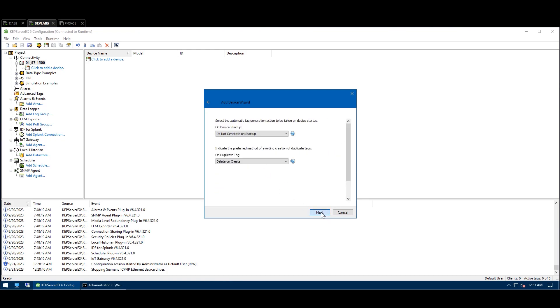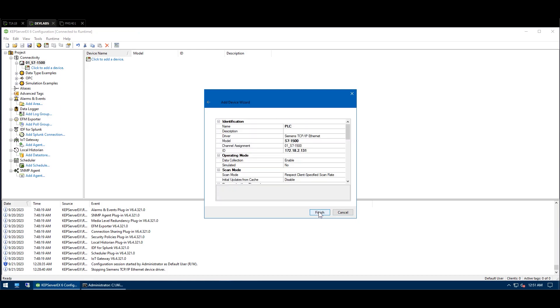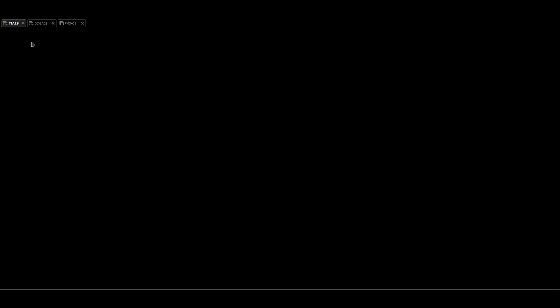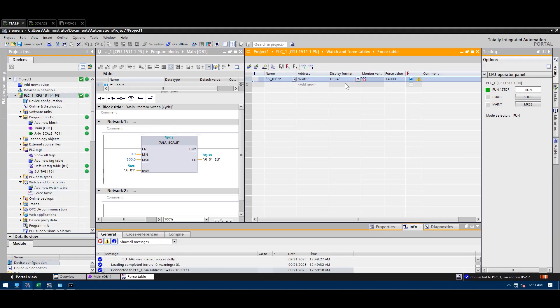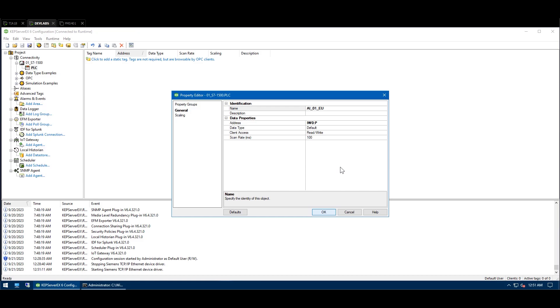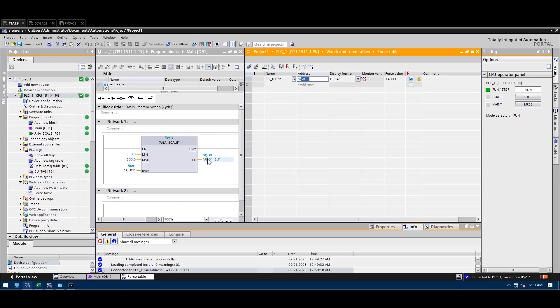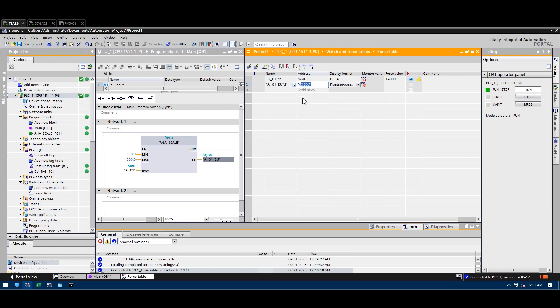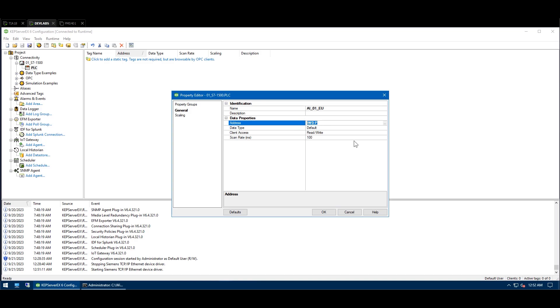Click Next — port 102 is the common one used for S7 communication. Done. Now I'm going to add the address. The easiest way to get the address is to look at the Force Table in TIA Portal and copy-paste the address. This is AI01 — actually it's the input, so I should take this address from the Force Table and paste it here.